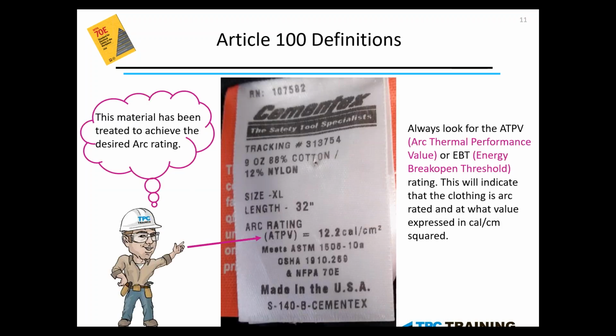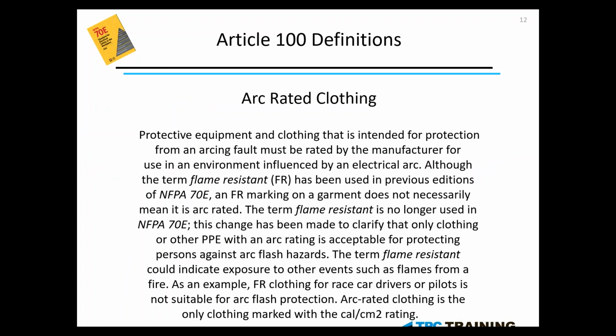So while we're looking at our clothing, we also want to pay close attention to the identifiers in calories per centimeter squared, whether it's ATPV, EBT, or FR. This is not identifying the fact that FR is no longer going to protect us. It's just the term is changing from that to the other two. And this is that explanation real quick of the change in terminology from FR to ATPV. You see again at the bottom of this paragraph right here where it identifies the fact that they are all identified in calories per centimeter squared.